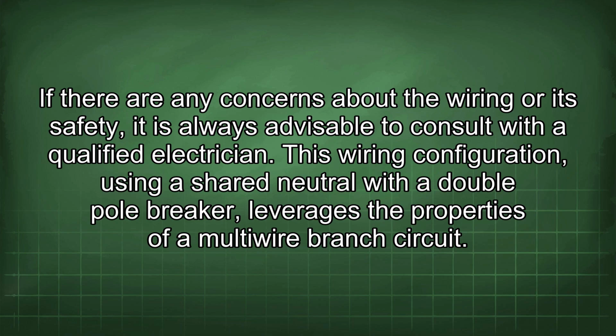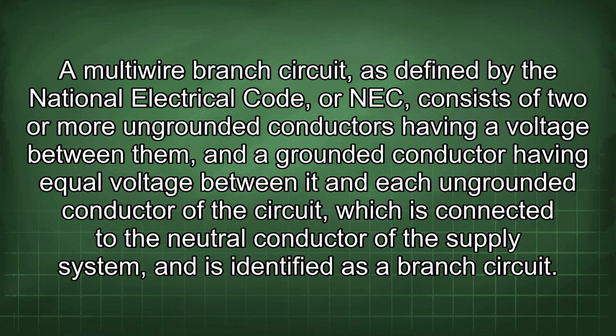This wiring configuration, using a shared neutral with a double pole breaker, leverages the properties of a multi-wire branch circuit. A multi-wire branch circuit, as defined by the National Electrical Code, or NEC, consists of two or more ungrounded conductors having a voltage between them, and a grounded conductor having equal voltage between it and each ungrounded conductor of the circuit, which is connected to the neutral conductor of the supply system, and is identified as a branch circuit.